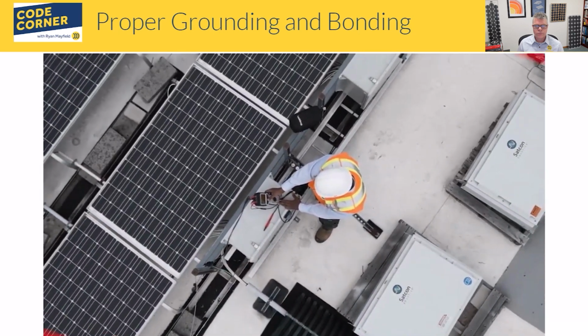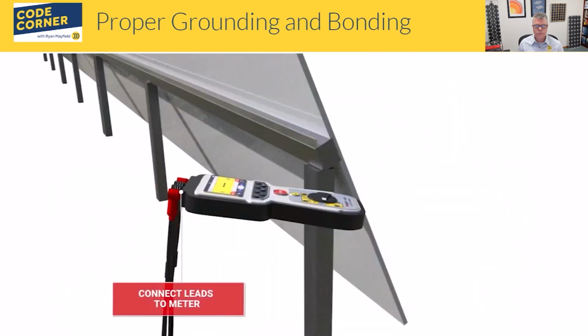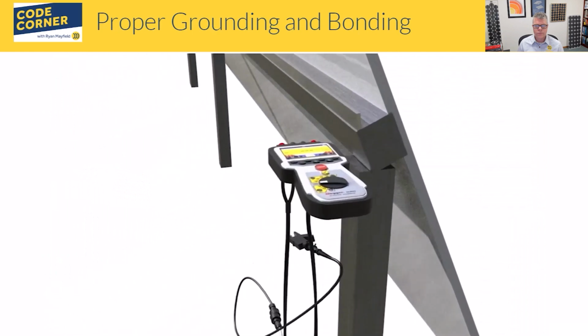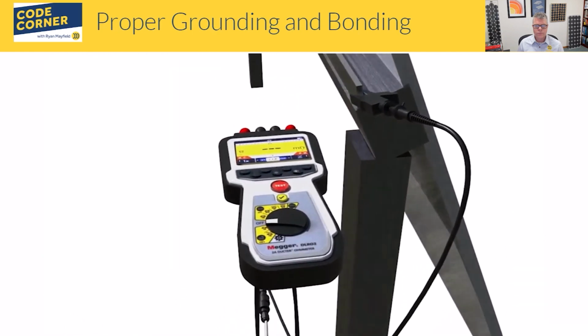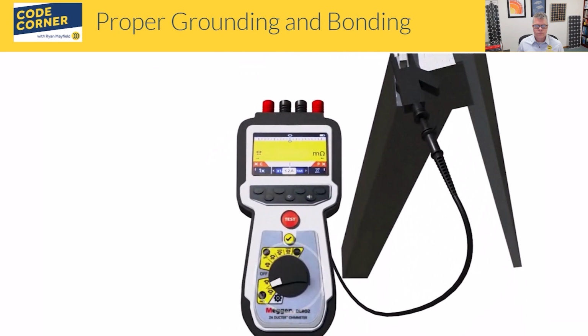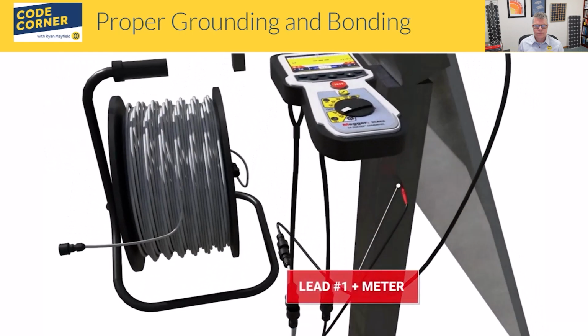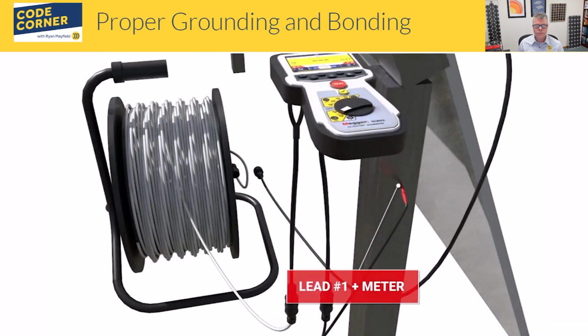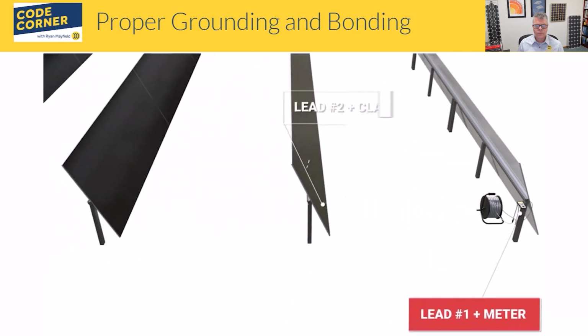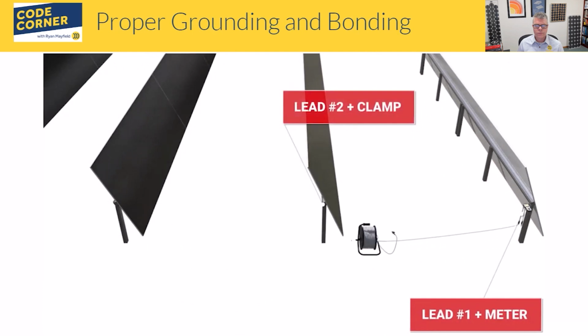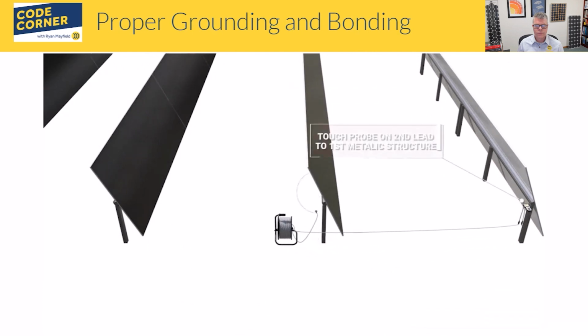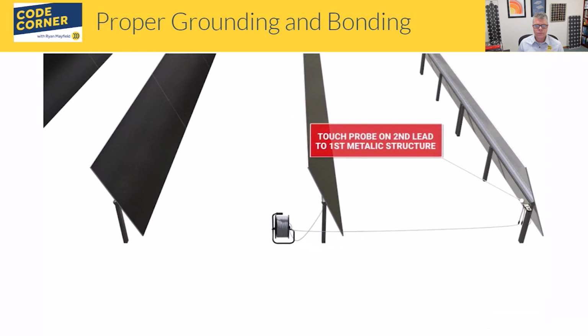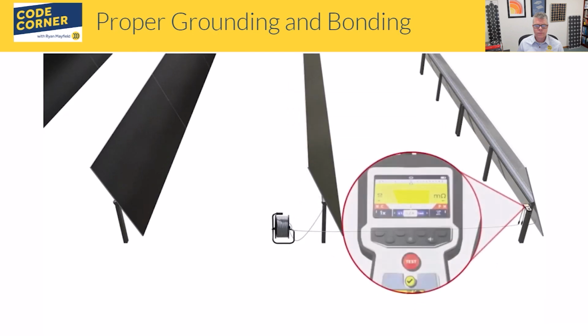To perform the test, a technician should connect the leads to the DLRO meter. Adjacent components should be tested to verify proper continuity. To test components spaced apart, an extension spool can be used. One lead remains connected to the meter, and the other will be connected to the extension spool and clamped to a metallic component up to 100 meters away. Once the clamp is attached, touch the probe on the second lead to the first metallic structure. Press the test button on the DLRO, and the resistance between the 2 points will be measured.